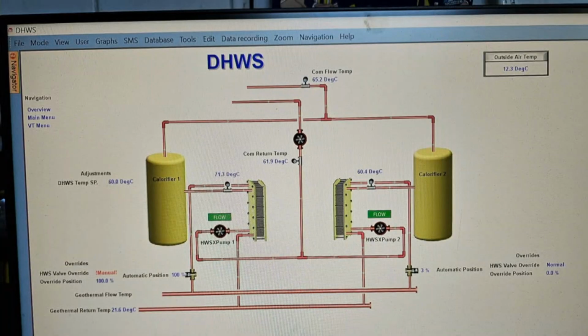You've got some errors on there. You've got valve positions. The nearest valve to me, down here, 100%. The valve on the opposite side of the system is at 3%. Why is there a difference? Why are them valves fully open? No valve should ever be fully open. It should always be modulating into a mid-position at the very most. So everyone thinks the information's correct, but there's inaccuracies in the information that people don't pick up on until you start putting monitoring in there, and then you can suddenly see this stuff jumping out at you.